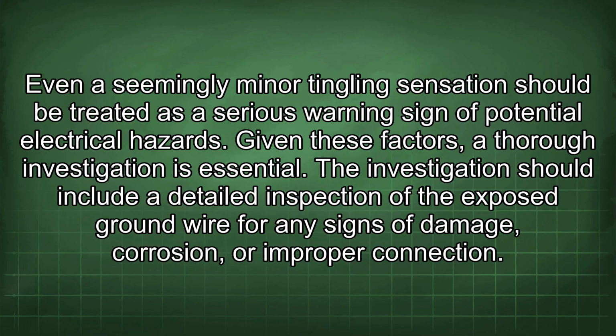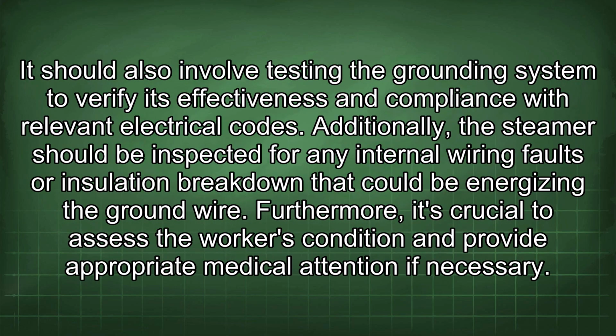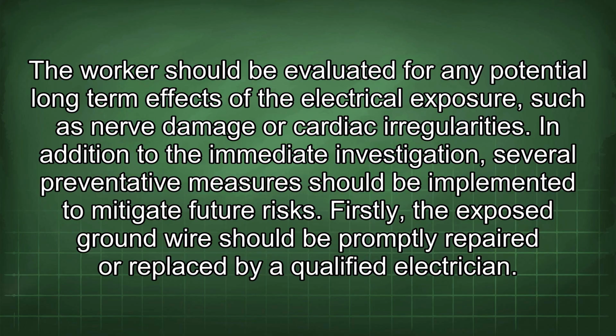The investigation should include a detailed inspection of the exposed ground wire for any signs of damage, corrosion, or improper connection. It should also involve testing the grounding system to verify its effectiveness and compliance with relevant electrical codes. Additionally, the steamer should be inspected for any internal wiring faults or insulation breakdown that could be energizing the ground wire. Furthermore, it's crucial to assess the worker's condition and provide appropriate medical attention if necessary. The worker should be evaluated for any potential long-term effects of the electrical exposure, such as nerve damage or cardiac irregularities. In addition to the immediate investigation, several preventative measures should be implemented to mitigate future risks.